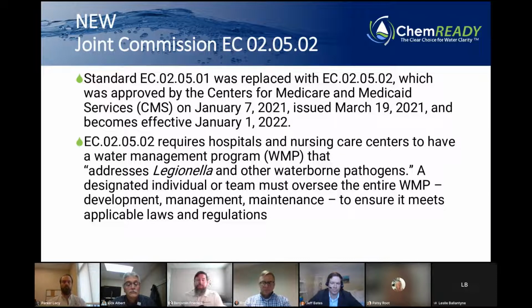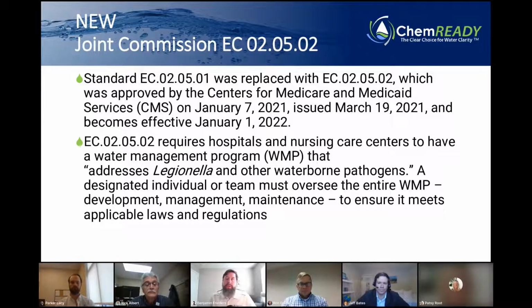This brings us to the new requirements of 2022. Up until this point, this has all been in regulation since 2018, when CMS placed guidelines. Last year, issued in March, the Joint Commission strengthened their requirements and stance on Legionella water management plans. They updated their Environment of Care Standard 02.05.01 with 02.05.02, which now requires and strengthens the language for hospitals and nursing care centers to have a water management program addressing Legionella and other waterborne pathogens.